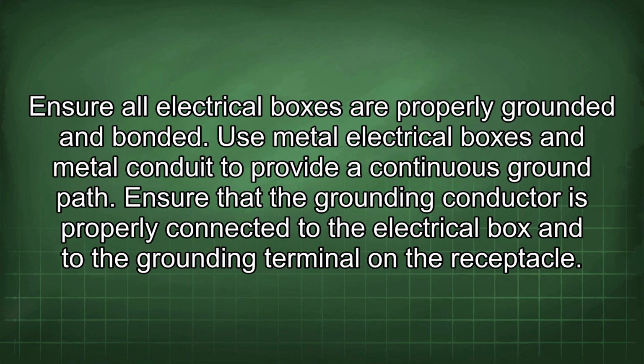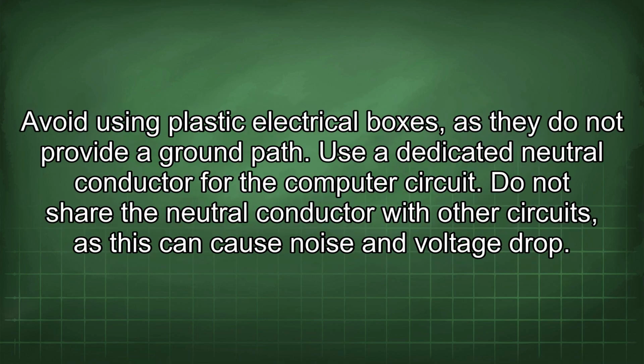Ensure all electrical boxes are properly grounded and bonded. Use metal electrical boxes and metal conduit to provide a continuous ground path. Ensure that the grounding conductor is properly connected to the electrical box and to the grounding terminal on the receptacle. Avoid using plastic electrical boxes, as they do not provide a ground path.